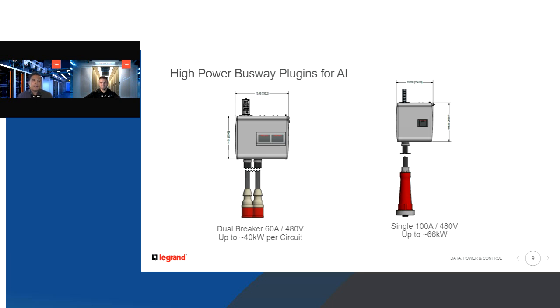On the plug-in side, we're also seeing this increase in power. For context, around 8 to 10 years ago, a 30 amp 208 volt or 30 amp 415 volt circuit was very common in the data center space. For AI, we're currently deploying 60 amp 415, but that same product can be customized to go up to 480 as well. We're very commonly deploying these 60 amp circuits to AI racks, and today we're seeing the use of a multi 60 amp circuit powering an AI rack.